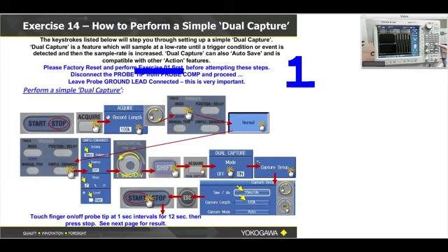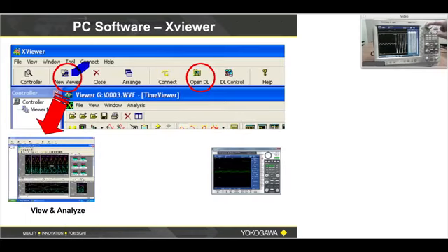At my fingertip here, I have an acquisition count. I have 57 events. If you look at your display where my finger is now, you'll see an event counter there. Everyone press stop. Okay, soft menu button number 4 says list. Go ahead and press list. However many events you've got in there, I've got 87. So it's a total of 88 events, 0 through 87.